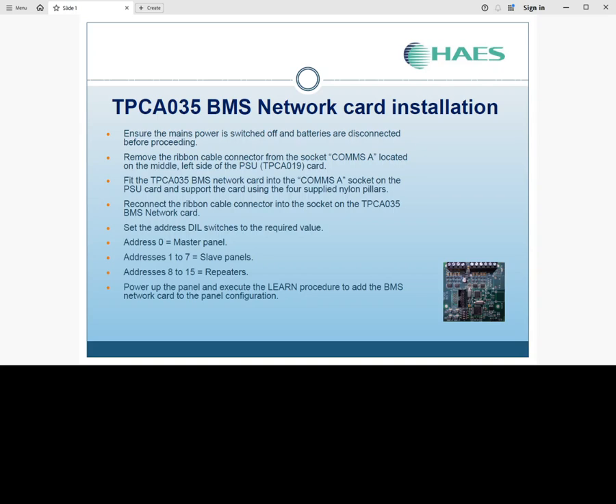Set the address DIL switches to the required value. If it's the master, it will be address 0. If it's a slave panel, it will be within the addresses 1 to 7. And if it's a repeater, it will be within the address range of 8 to 15. Power up the panel and execute the learn procedure to add the BMS network card into the panel configuration.